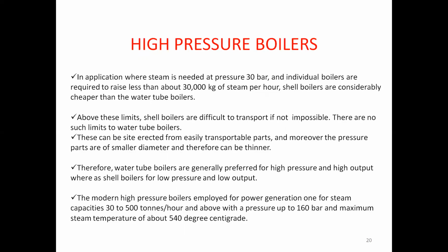Shell boilers are considerably cheaper than water tube boilers. But with water tube boilers, we get a large quantity of steam with high quality. So that is important. Therefore, water tube boilers are generally preferred for high pressure and high output, whereas shell boilers are for low pressure and low output. One important point he is mentioning: water tube boilers are generally preferred for high pressure and high output, whereas the shell boiler is considered low pressure and low output, internally fired, externally fired.